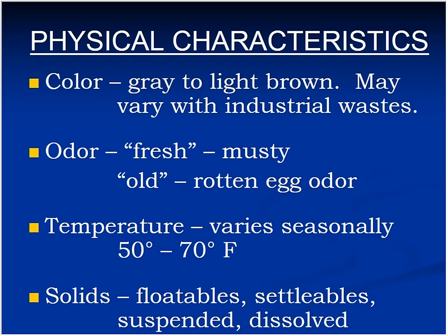The whole collection system is being put under scrutiny through a process that we refer to as CMOM, Capacity, Management, Operation, and Maintenance. It basically says that you have to maintain your collection system and inspect it on a regular basis, find those leaks, cut out the tree roots and all that stuff, and deal with the grease issues. There's been increasing enforcement on that end over the past several years. Physically, when we look at the water coming into the plant, it's typically gray to light brown.